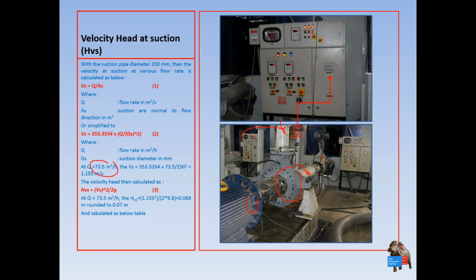Of course, by formula you can get what we call the velocity head at suction and also the velocity head at discharge. At this point you also collect the speed of the shaft, you collect the pressure at the suction and the pressure at the discharge, and here there is a power meter. You also collect the power into the motor at that specific flow capacity.